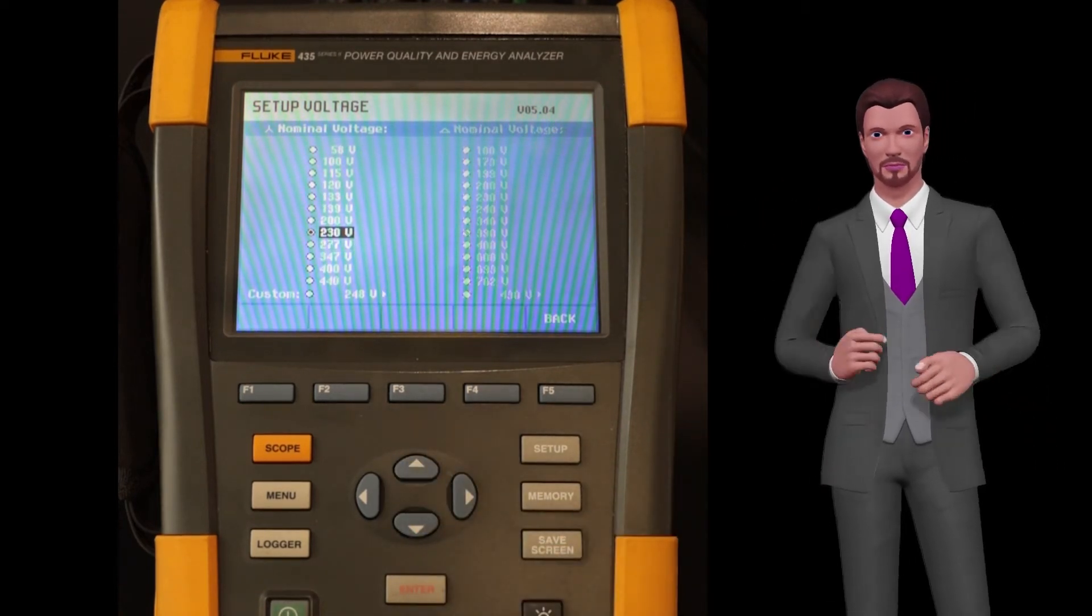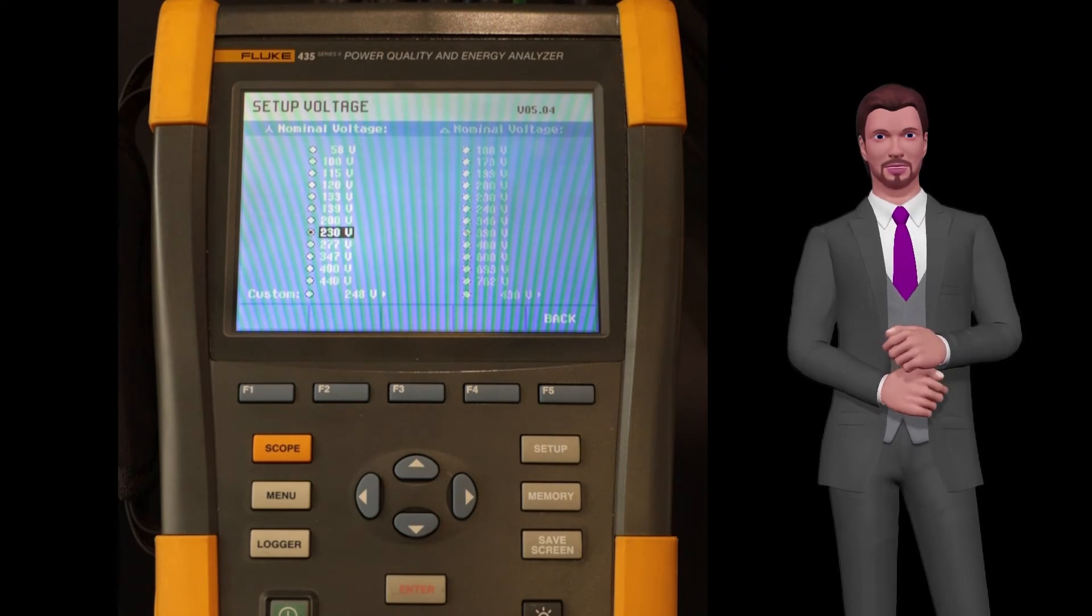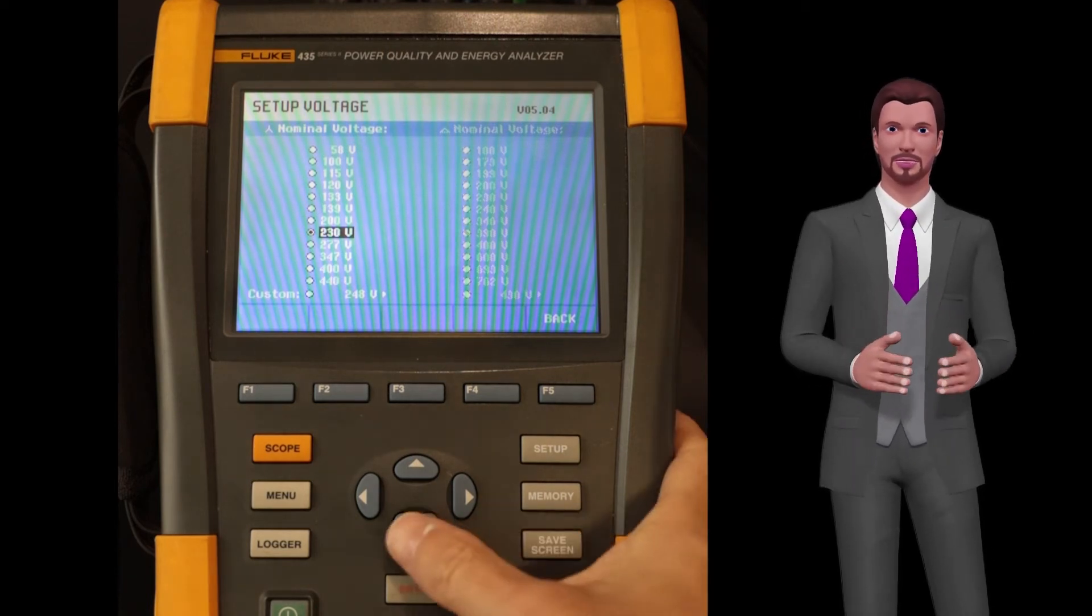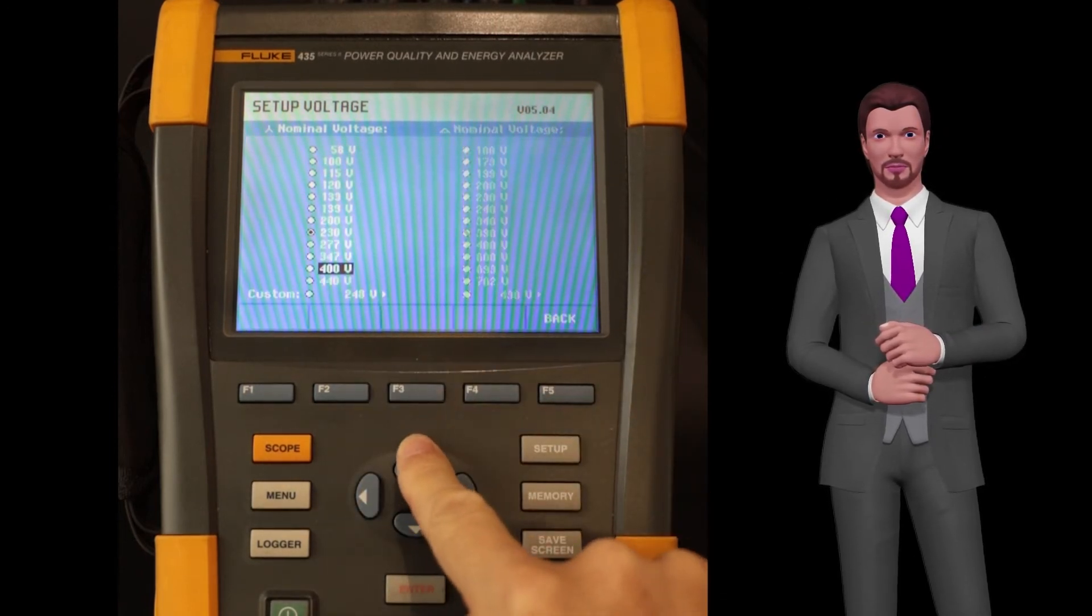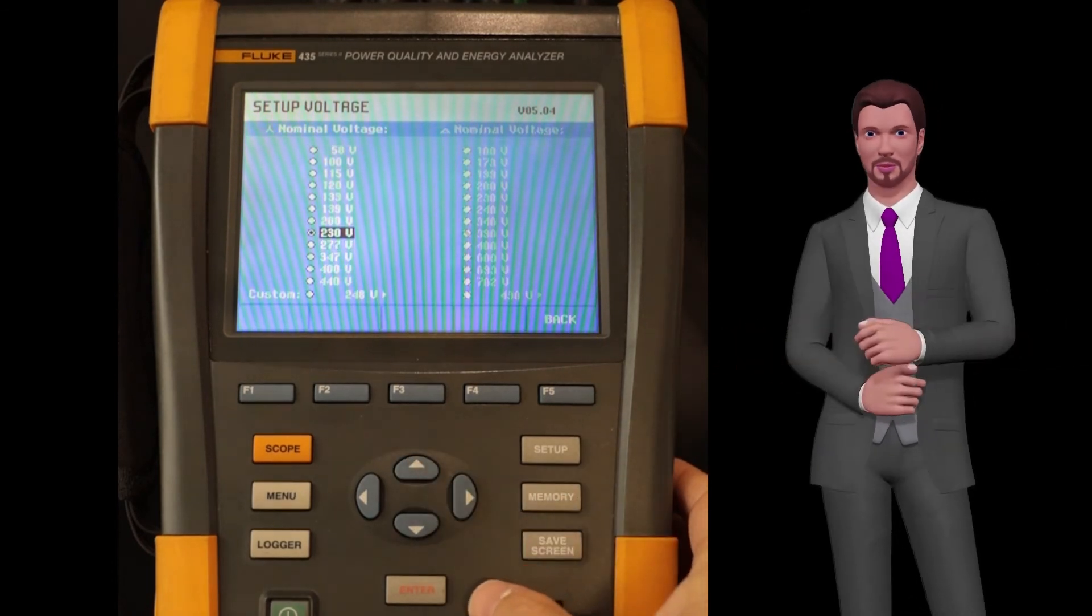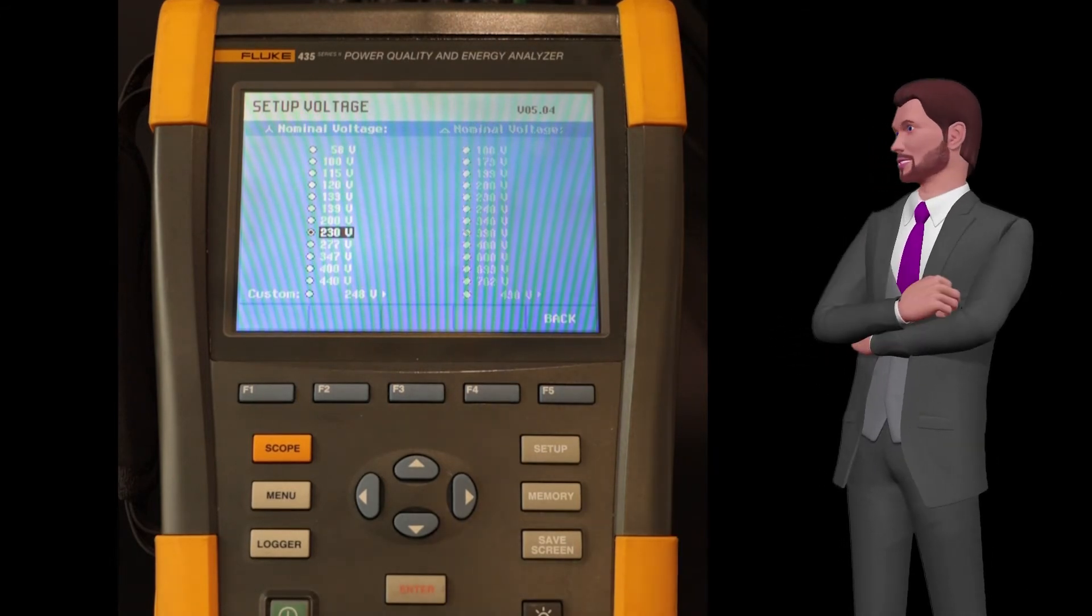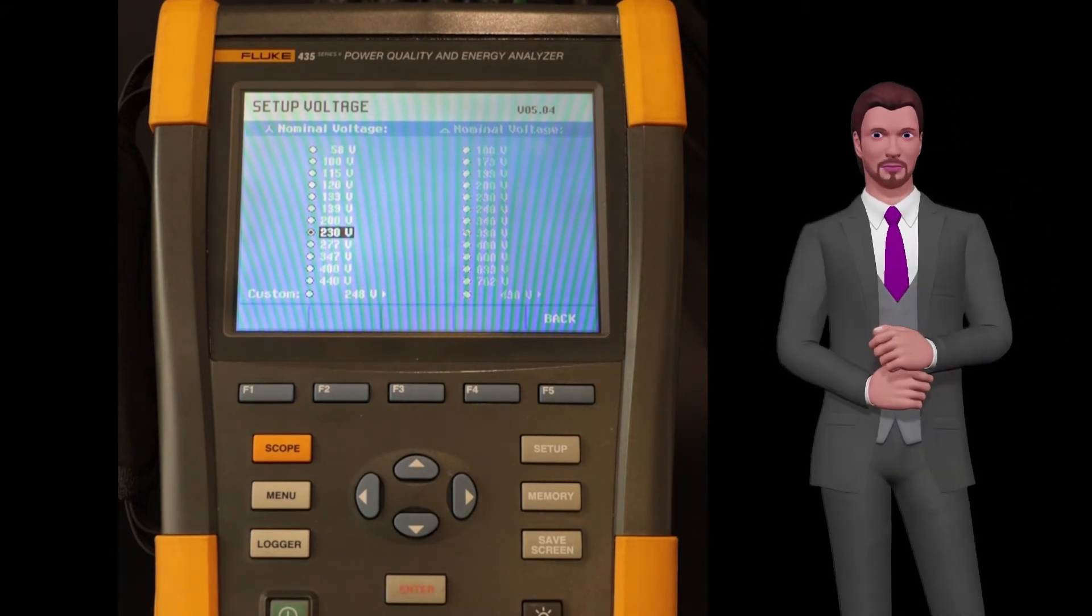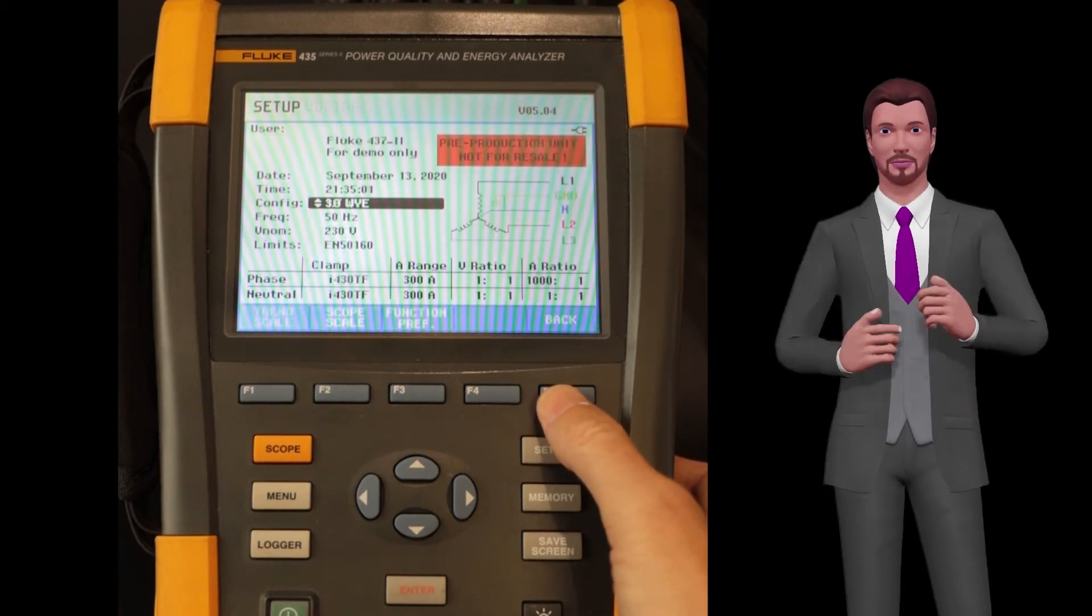This is very important because if we put a value of 400 volts, when measuring a real value of 230 volts between phase and neutral, the unit will think that a voltage drop is permanently occurring. Therefore, in summary, in a delta configuration we need to provide the voltage value between phase and phase, and in a star configuration, we need to provide the voltage value between phase and neutral.